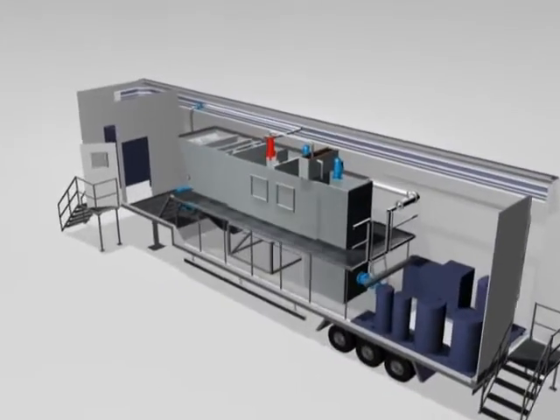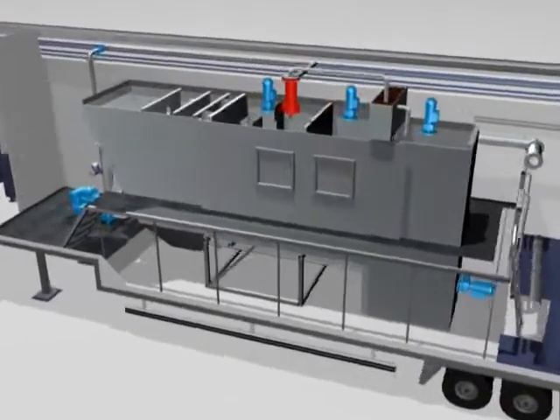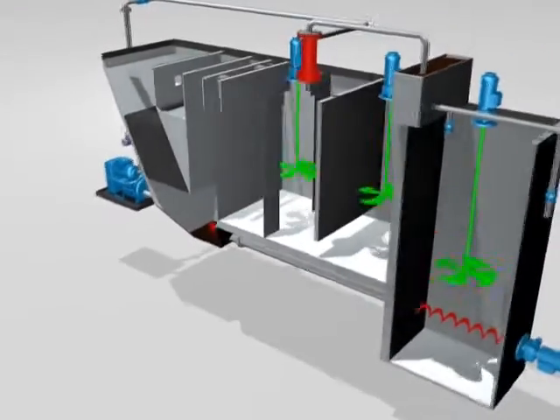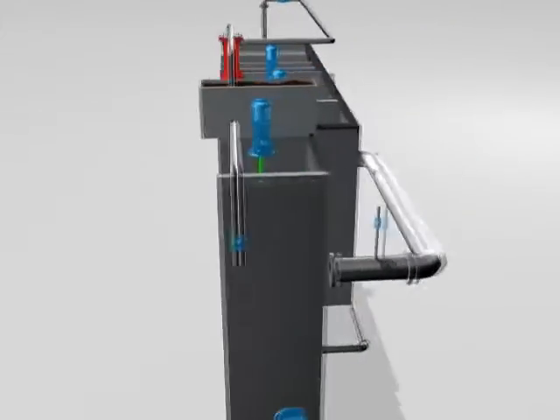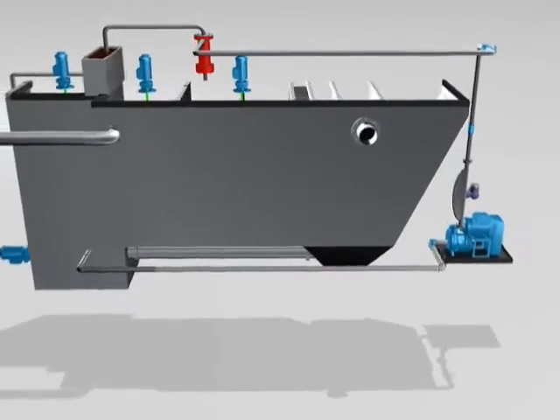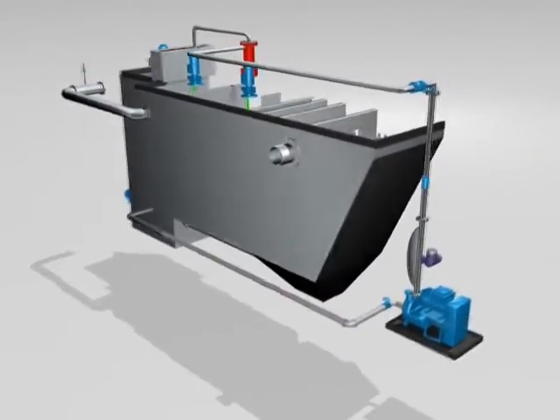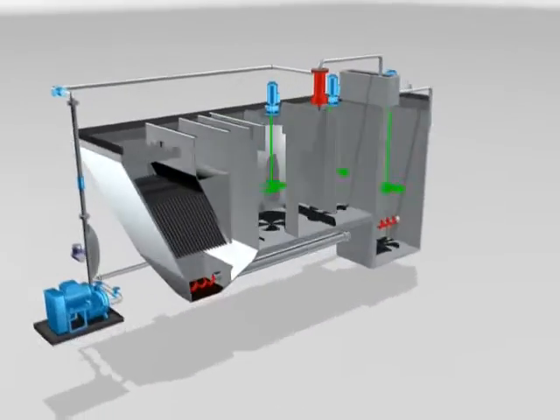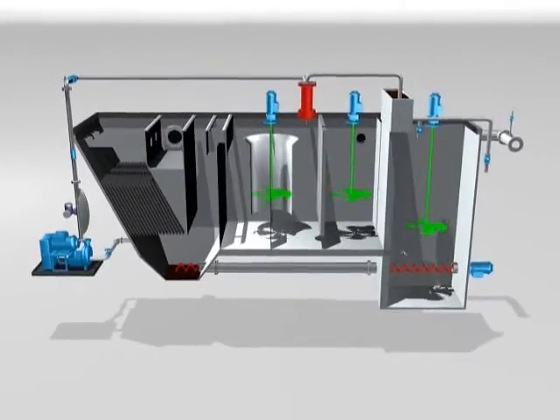The microsand provides surface area for floc formation and acts as a ballast. The resulting microsand ballasted flocs display unique characteristics which allow for clarifier designs with very short retention times, high rise rates, and extremely compact system footprints that are between 5 and 50 times smaller than conventional clarification processes of similar capacity.